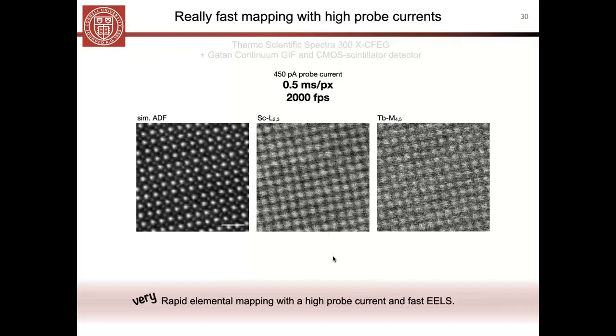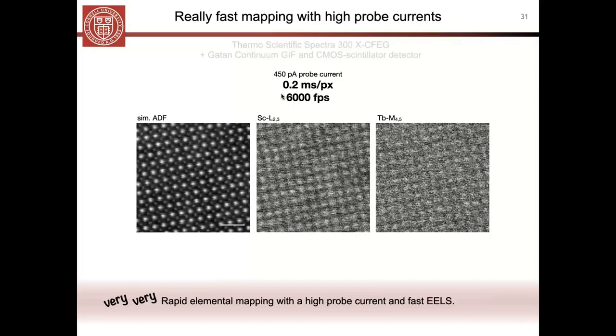If you want to really push the limits, we've dropped the readout speed by more than a factor of 10 from the cryogenic maps shown earlier, running at 0.2 milliseconds per pixel. This is the maximum frame rate of the continuum GIF and CMOS with scintillator detector on this instrument—a much bigger increase, down to 6,000 frames per second—letting us do very rapid elemental mapping.